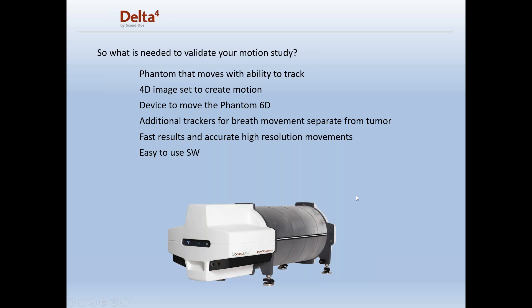What do you need to validate motion? First, you need a phantom that can track and give you the ability to see the radiation being delivered to a target. You also need a 4D image set so you can create a motion field, and a device that's going to move the phantom six-dimensionally, plus the ability to track breathing separately.